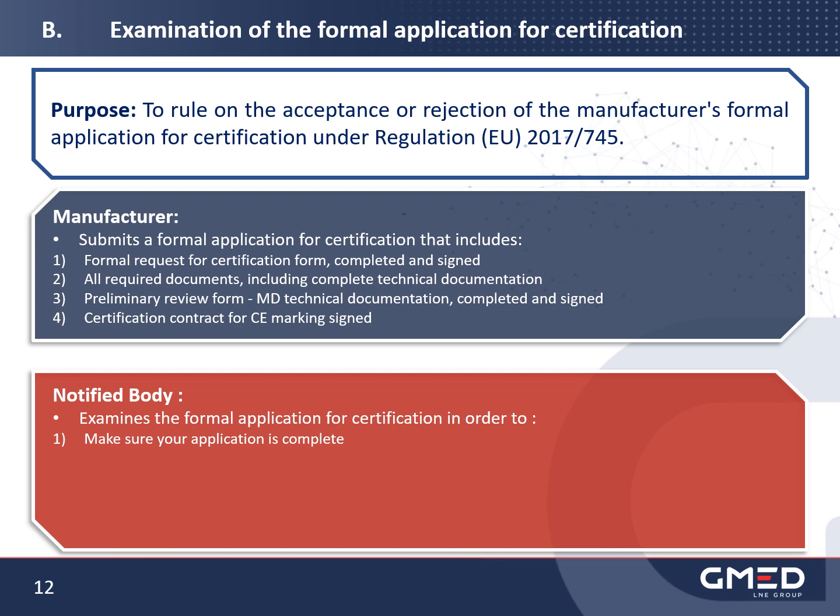As part of the examination of the formal application for certification, GMED's intervention is limited to verifying the completeness of the formal application for certification and certain parameters and aspects that have a direct impact on the certification process, such as a check that the products covered by the application are medical devices and that their classification is appropriate.